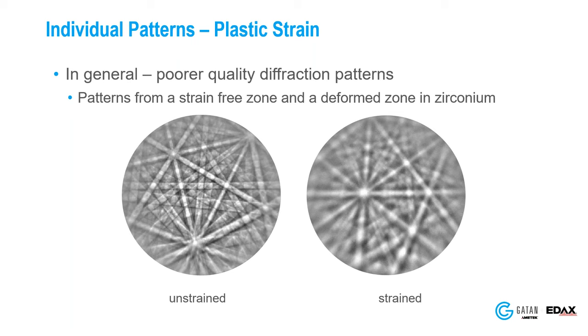Question: What can I do if only half the Kikuchi pattern is well-defined? If there's enough for the Hough transform to detect the bands, you'll be fine. We also have newer techniques based on what we call pattern matching, which are much better at dealing with rough surfaces where you may have shadowing or intensity gradients across the pattern. For really difficult surfaces — as-deposited or fracture surfaces — you may want to use these new techniques, and there are various tools and modules in the software to help. Even on a rough surface, a quick broad beam ion polish can clean up some of these issues.